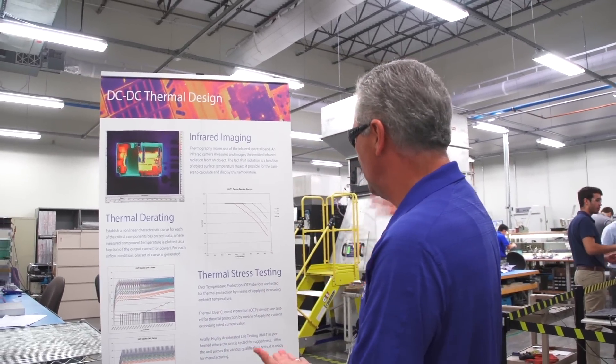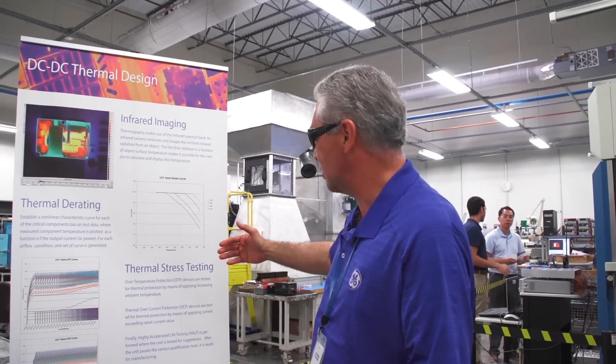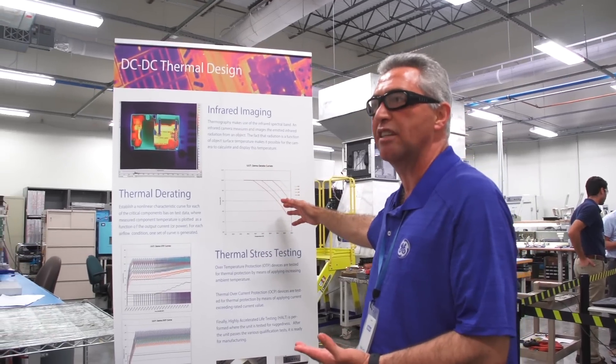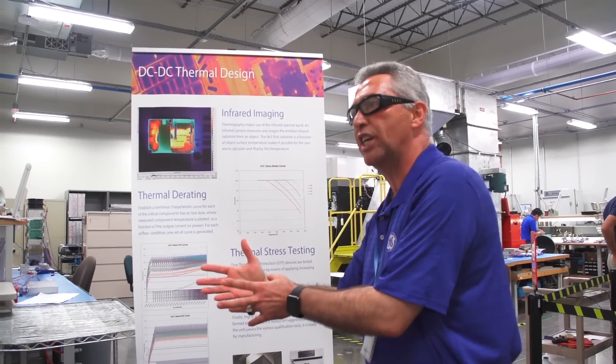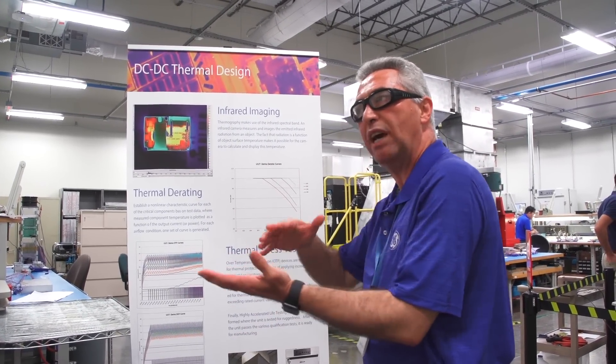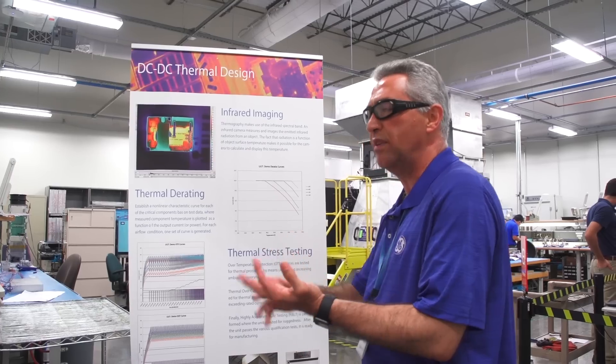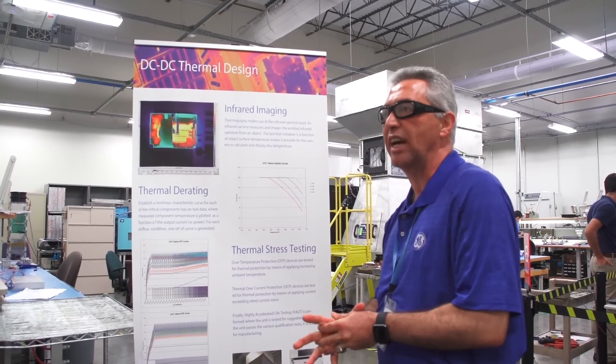So what our guys do, using a wind tunnel testing that I will show you, is to provide derating curve for the customer that tells them, this is how much power you can get at this ambient temperature if you have this airflow. And we test at 200 feet per minute, 400 and 800 feet per minute for each test.